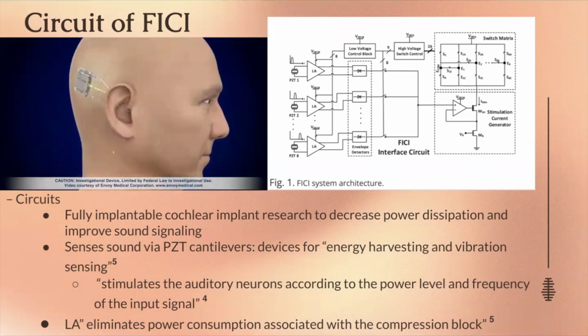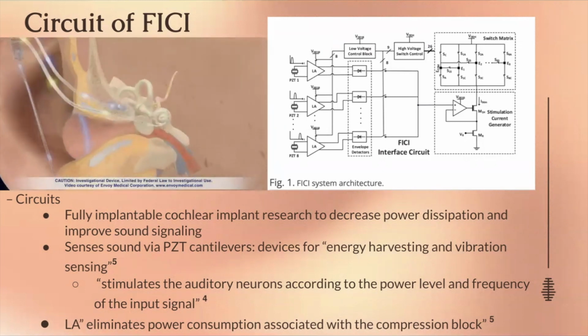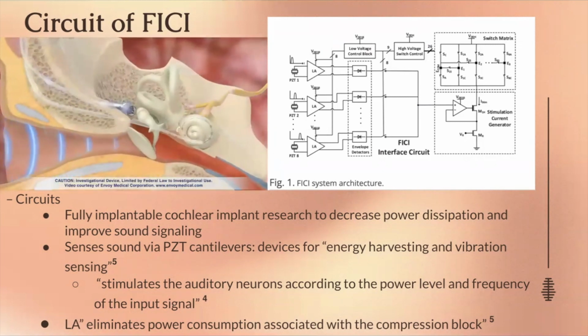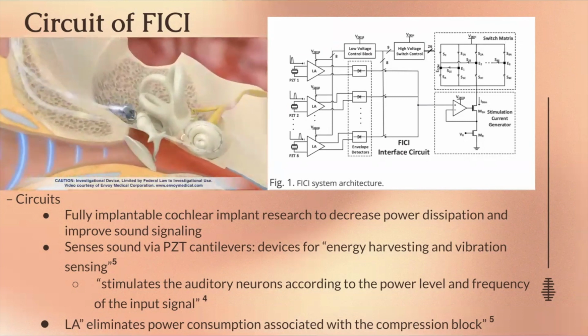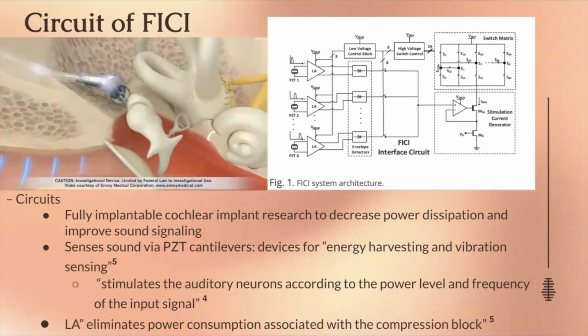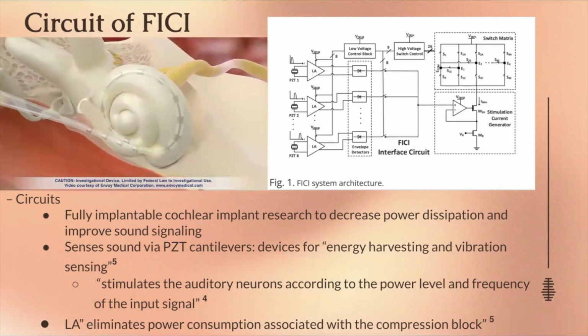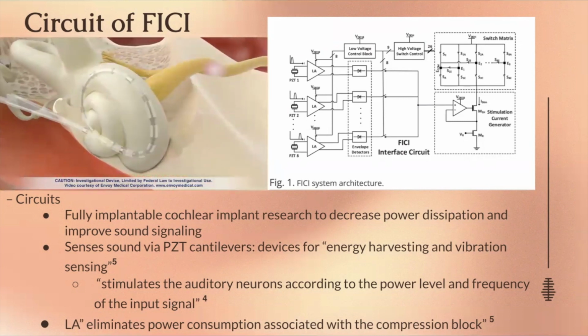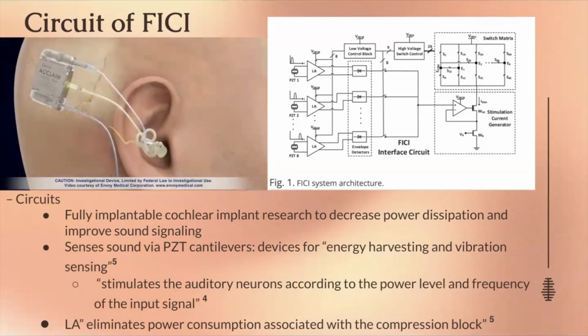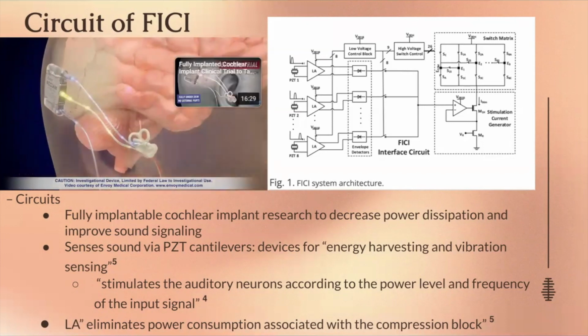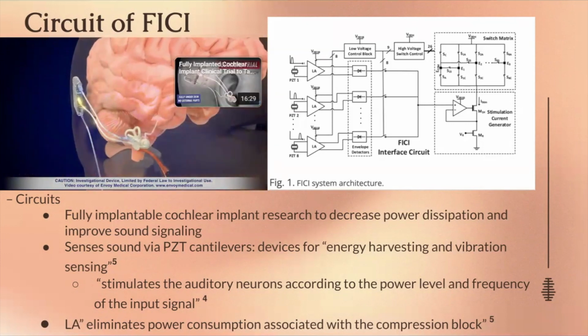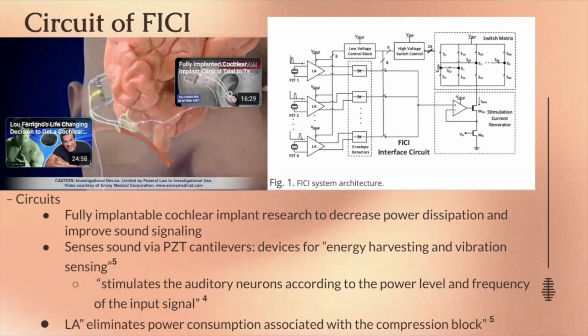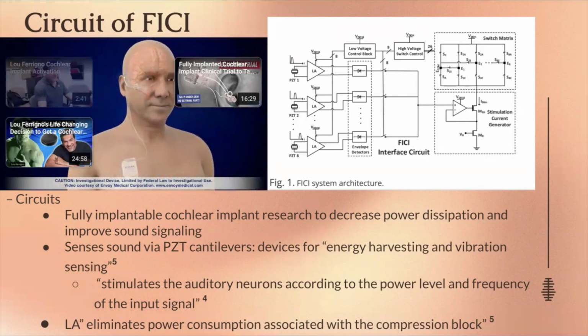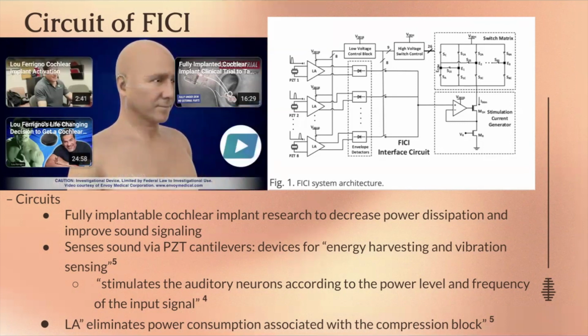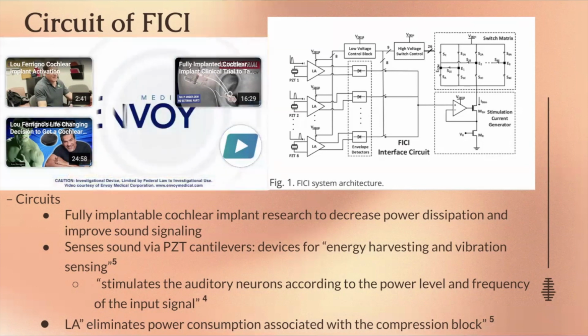And the study that I looked at also implemented a logarithmic amplifier to help amplify the PZT sensor output and compress the input sound range to the electrical range of the cochlea. An important change here was the use of the logarithmic amplifier at the first stage in this circuit, and the dual function of the amplifier to amplify and logarithmically compress signals eliminates power consumption associated with a compression block in many other circuits. And the main finding of this work is that the front-end signal conditioning circuit here has the lowest power consumption compared to previously done studies.